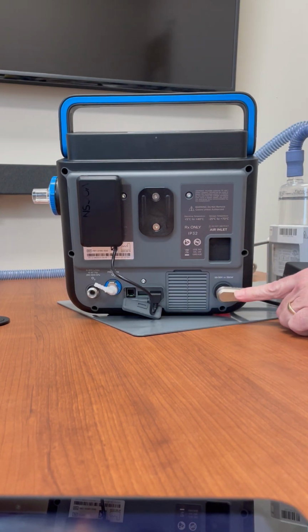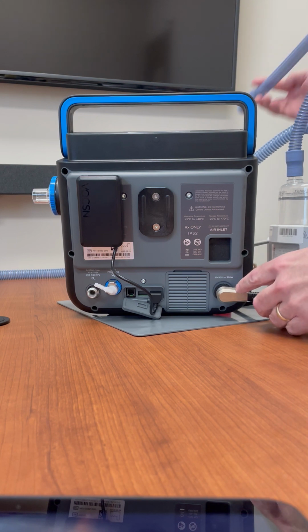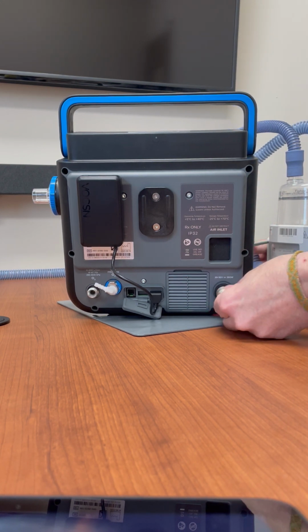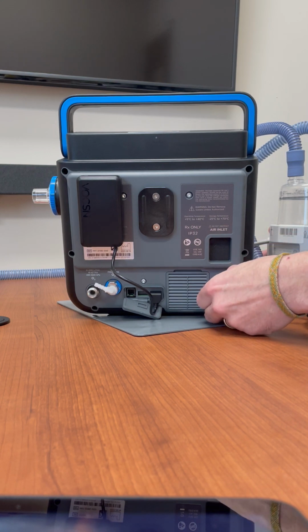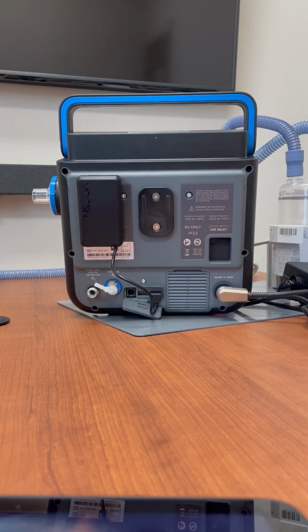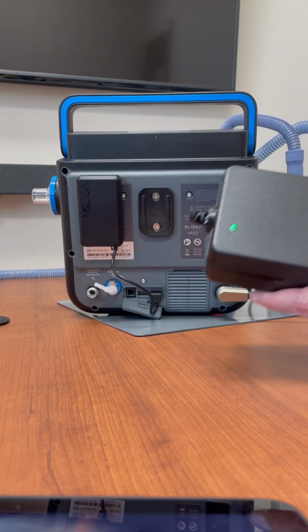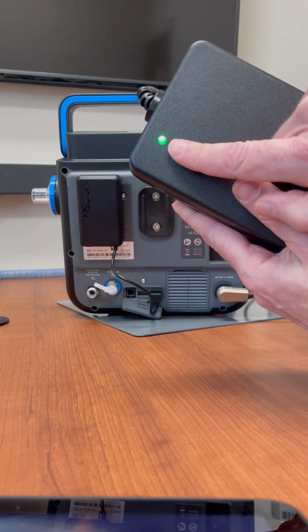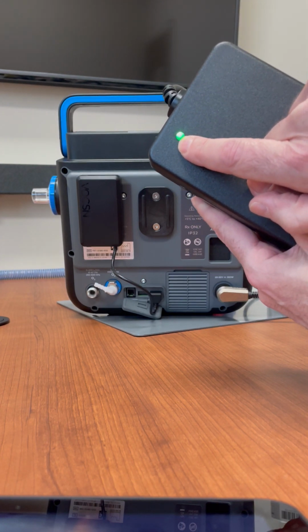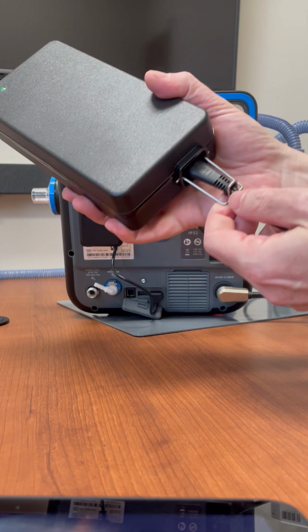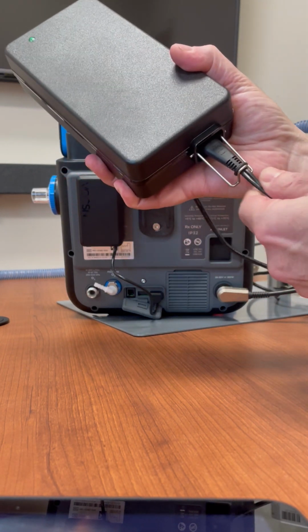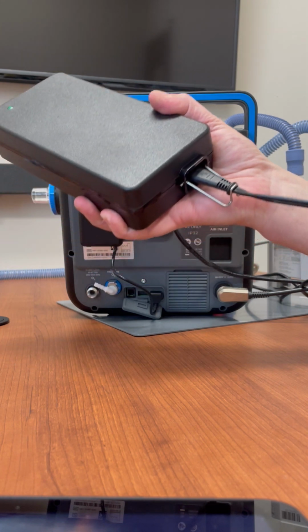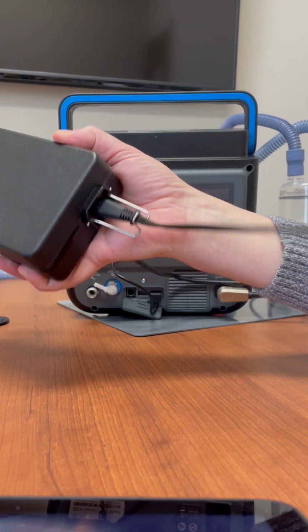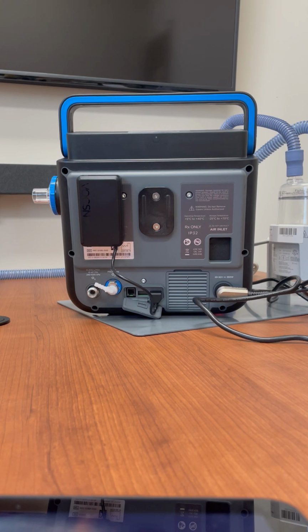And lastly is your power connection. That is a heavy-duty power cord that plugs into the back of the vent and screws on so that it cannot accidentally be knocked out and deplete the ventilator's batteries without the patient knowing. The cord first goes to this black reducer box, and you know it's plugged in because it has a green light lit up. And then the other cord is clicked into place, so again, it can't automatically fall out and drain the batteries. And then this cord plugs into the AC outlet of your wall.